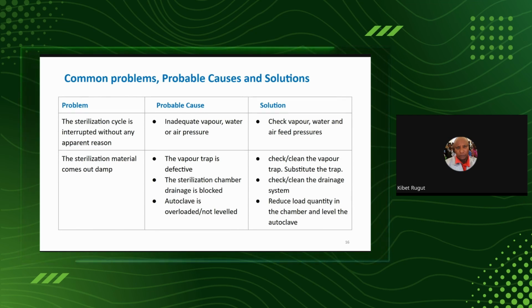The material that you sterilize comes out damp. I know most of us have been called up to attend such situations. There is a vapor trap, and that is a very important part of the autoclave to be checking all the time. Sterilization chamber drainage may be blocked. The autoclave may be overloaded, as we said earlier. And then the leveling is an issue too, because the water sensors and other sensors depend on the leveling of the chamber, so it will give a wrong signal. So you have too little or too much water in the boiler.